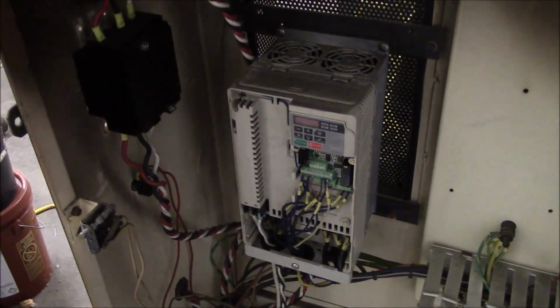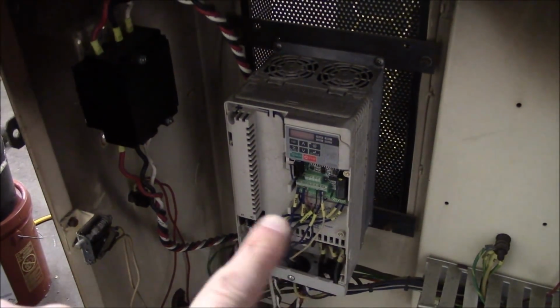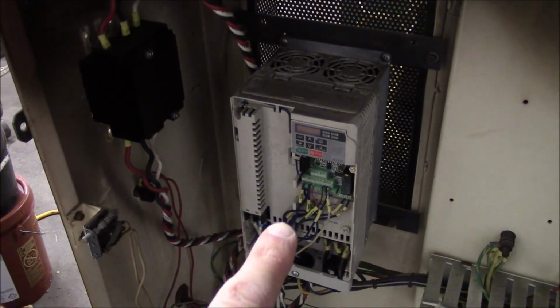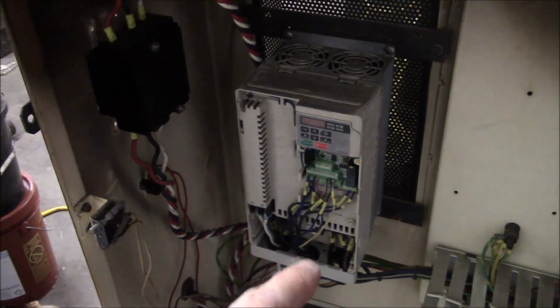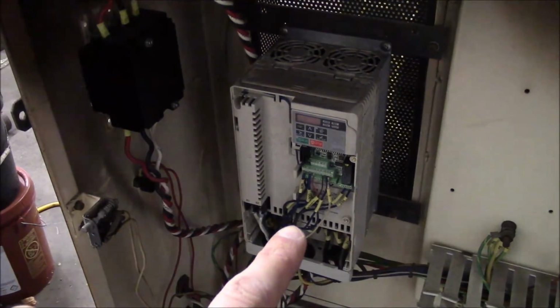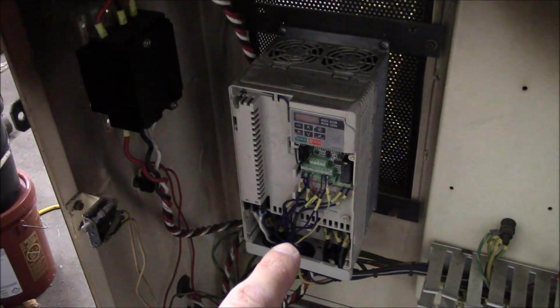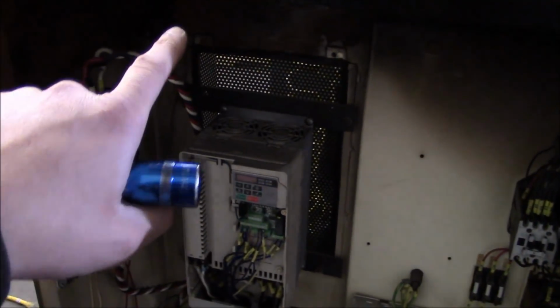It's almost happened to me twice. And what happens is the big IGBT modules inside the drive, when they fail closed, usually they just start pumping all the DC bus voltage into the braking resistor. So this is not the original braking resistor. It originally would have been mounted up here above the drive.